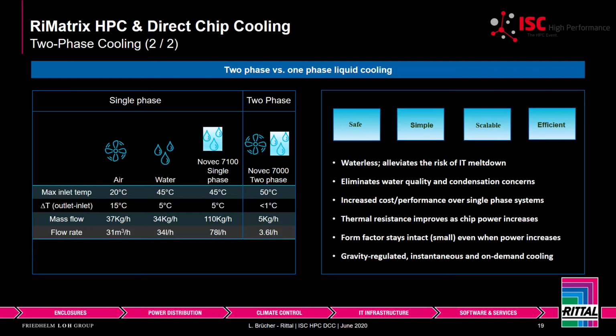In addition to this, if you're looking at the mass flow or the flow rate, by using a two-phase technology you're going to around 5 kilograms per hour of liquid flowing. Going to the air and water, you're showing 37 or 34 kilograms per hour. So the mass of volume that you need to circulate, because you're not using the latent energy, is huge. So you need bigger pipes, stronger pipes, and on top of this, you have no water on the servers. It's just a dielectric liquid, so there is no risk of spillage.